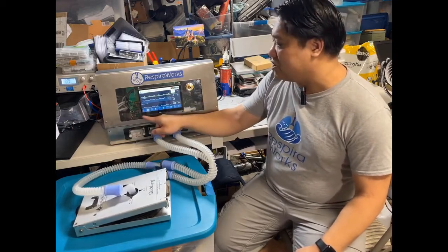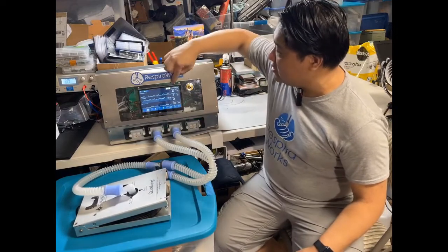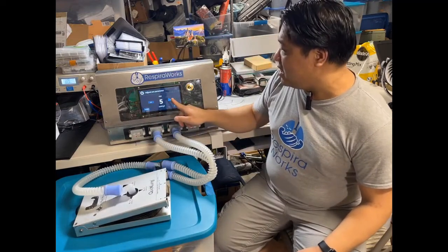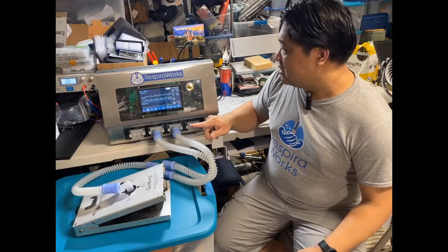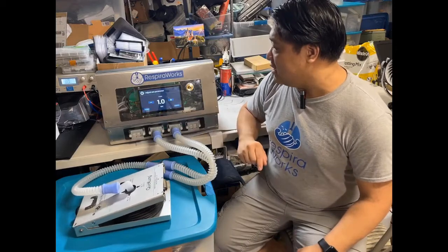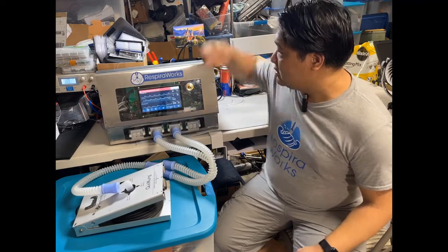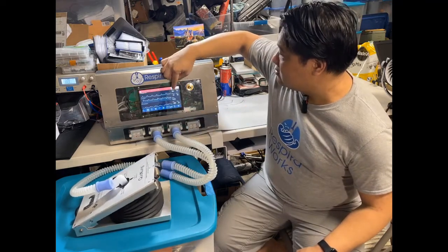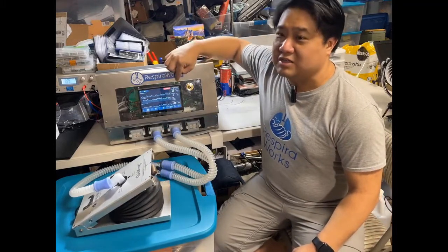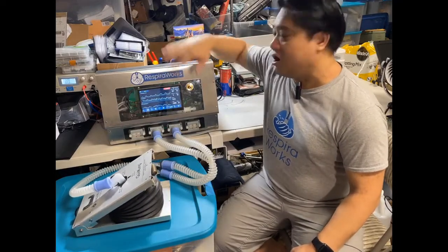So that rapid change in PIP set point did actually trigger an alarm, and we can hit pause here, and you'll see that the alarm continues to be persistent here. Let's set a PEEP of 10. And we'll ignore FiO2 for now because we don't have any oxygen connected. We can set an inspiratory time, so let's make that 2 seconds. And you'll see here that alarms also have a timer. So if an alarm is paused, when this timer runs out, it will reinitiate the visual and auditory alarm.